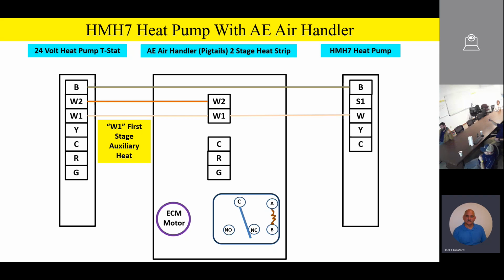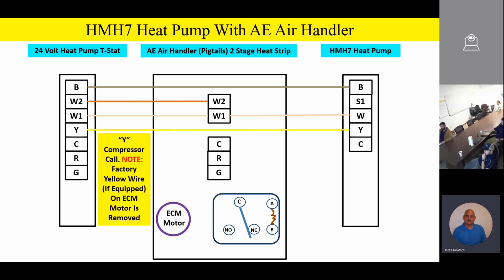Everybody good? All right. Y terminal from the thermostat is going to go through and it's going to hook up to Y outside. Now, this is very interesting about the HMH heat pump. We only need a single Y terminal outside. We don't have a Y1 or a Y2 outside. You're going to see why here in a little bit. So the unit outside is a fully modulating system, and it modulates from 35 to 100% capacity. And it does that with just a simple Y signal going outside from the thermostat.